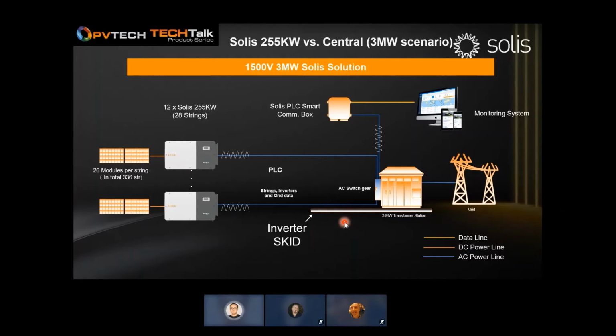So by removing the skid, we have done some study saying that on average, it will save you $10,000 to $20,000 US just by not installing the skid. We'll get rid of the skid. It depends on how big your project is. I'm using a 3 megawatt subarray as an example here. If your project is 10 megawatt, then you will be able to save 3 to 4 times the saving. If your project is 100 megawatt, then you will have almost 30 times the saving. And this number adds up very quickly.